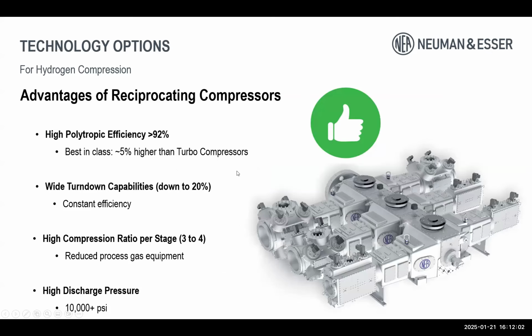Now, just for reference, why reciprocating compressors for hydrogen applications, as I mentioned on the previous slide. The number one reason to use a recip on a hydrogen project is efficiency. They have very high polytropic efficiency, around 92%, on average more than 5% higher than a similar turbo compressor for the same application. They can also have pretty wide turndown capabilities while delivering a constant efficiency. That means you can keep that efficiency very high even when you are turning down the capability.